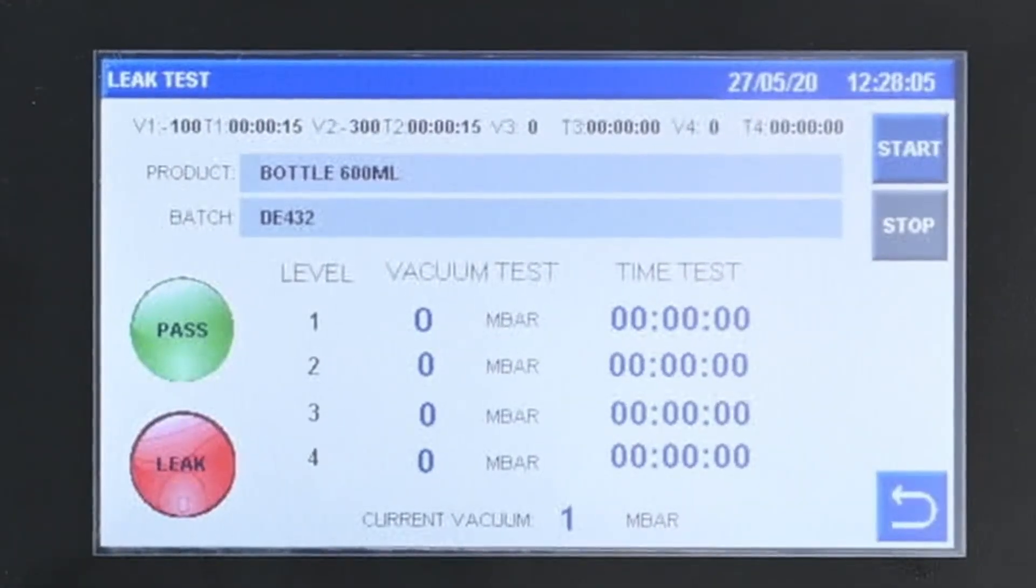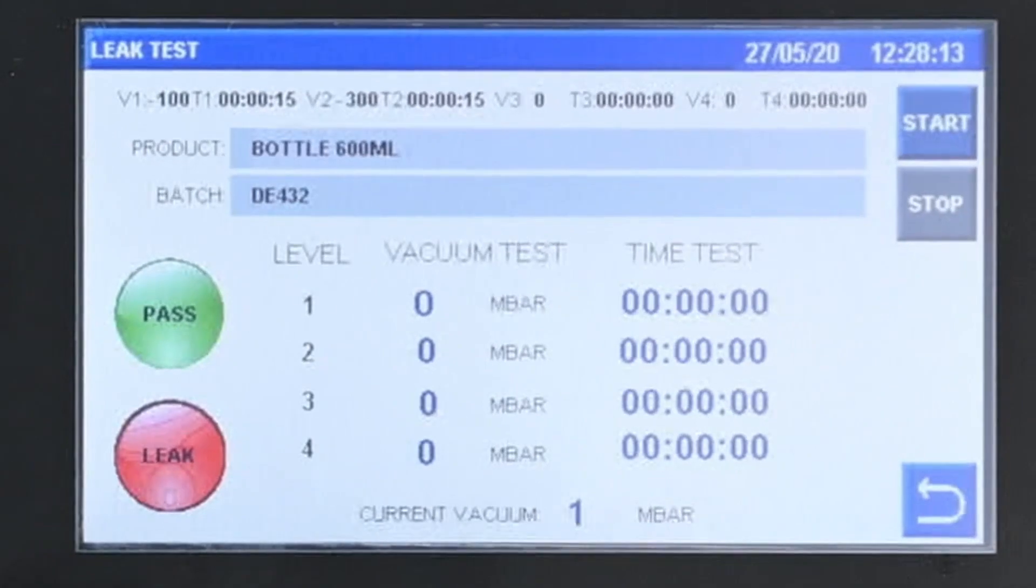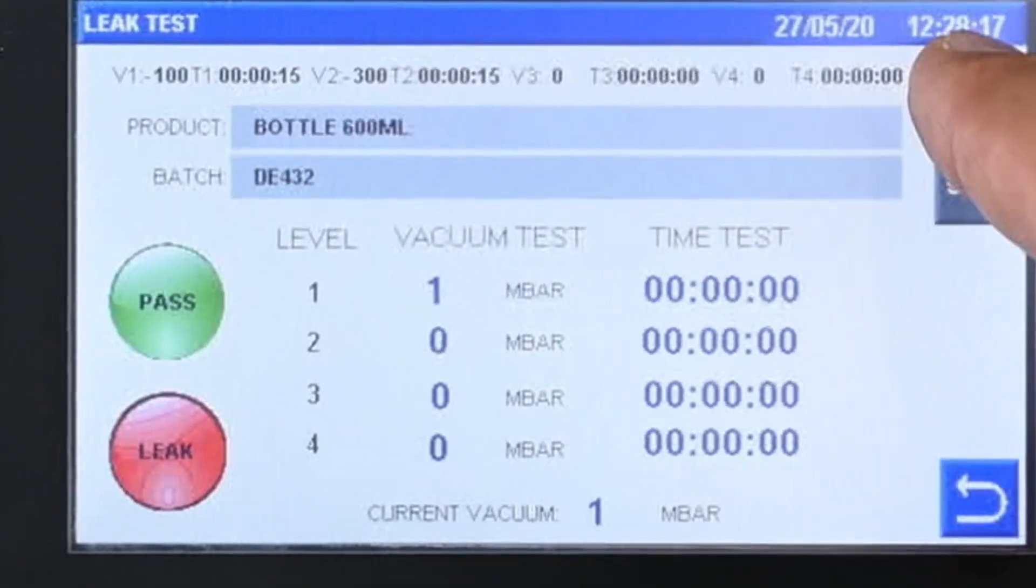Leak Test allows access to a library of up to 99 test recipes, each with four programmable time stages and vacuum.